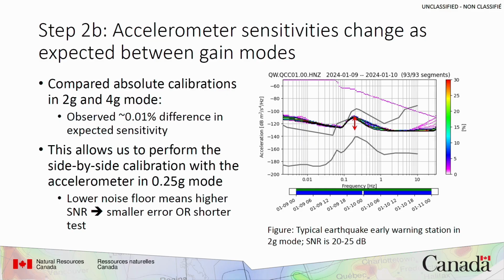I'm going to quickly get through this. The electrical calibration, I'm glossing over it a little bit, but I will note that there's a slight difference in the response of an accelerometer between DC and 0.2 hertz, which needs to be accounted for.